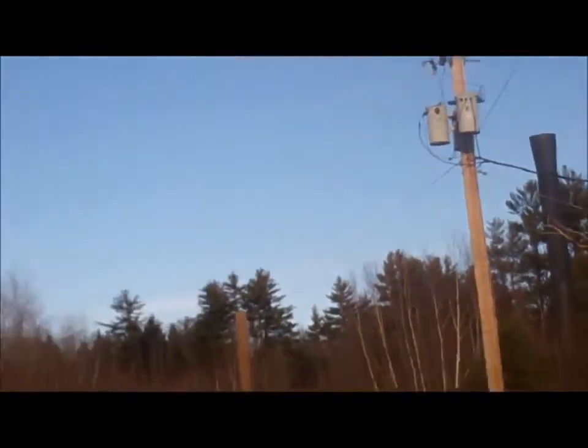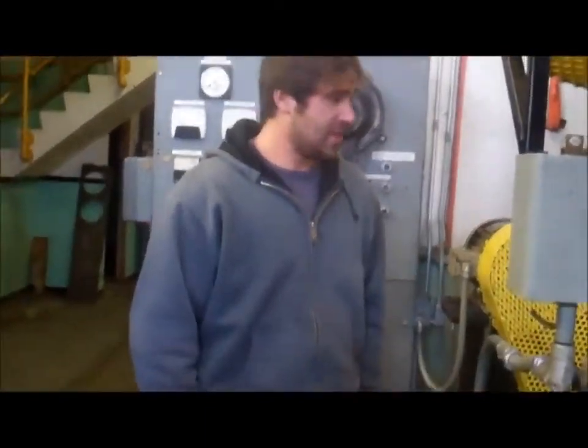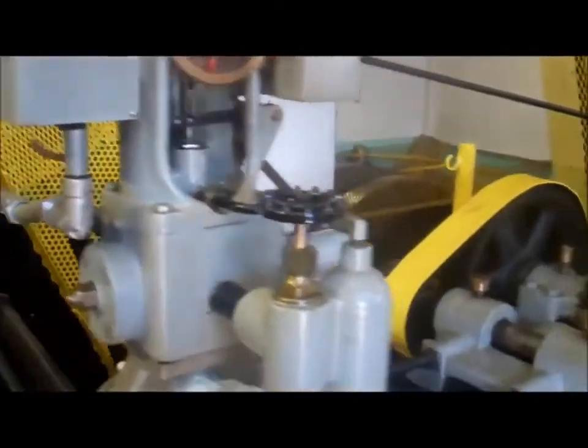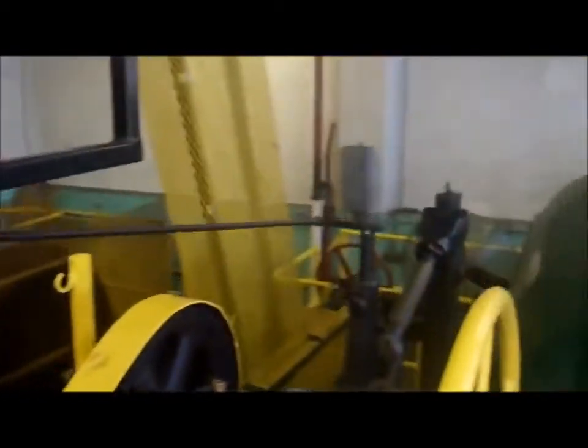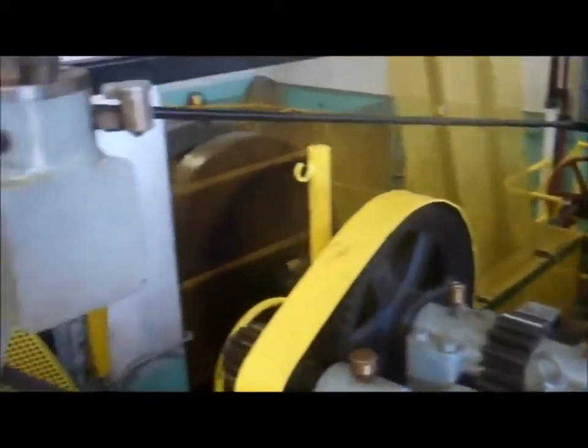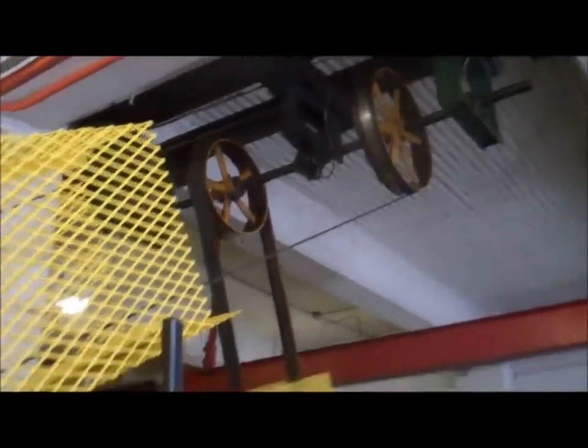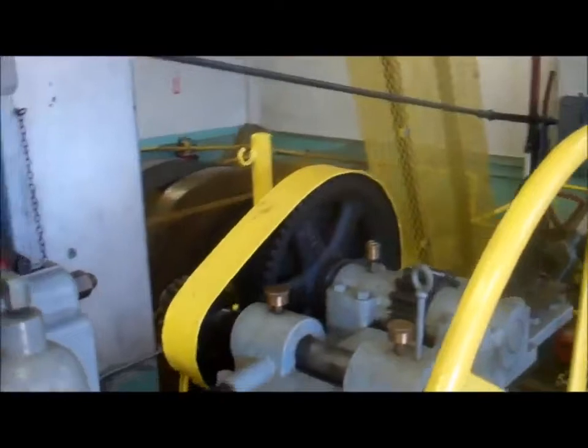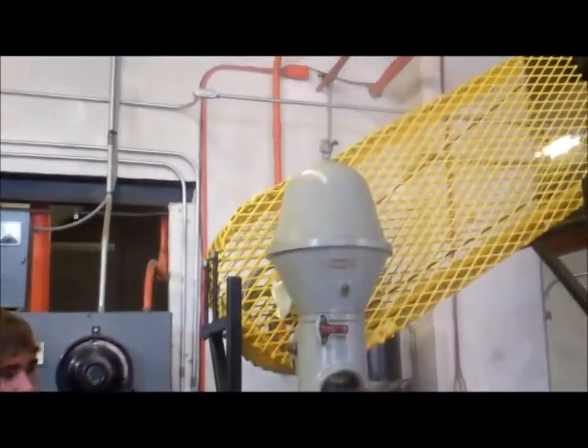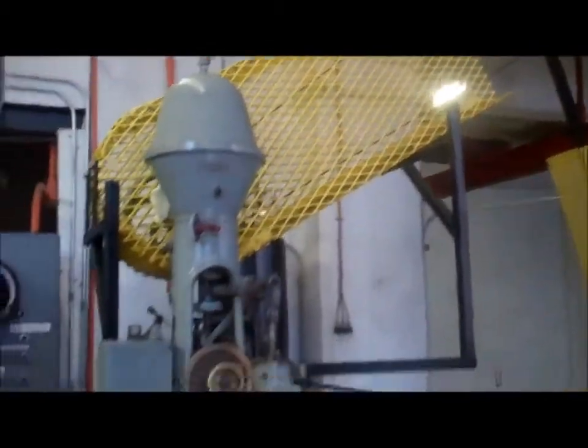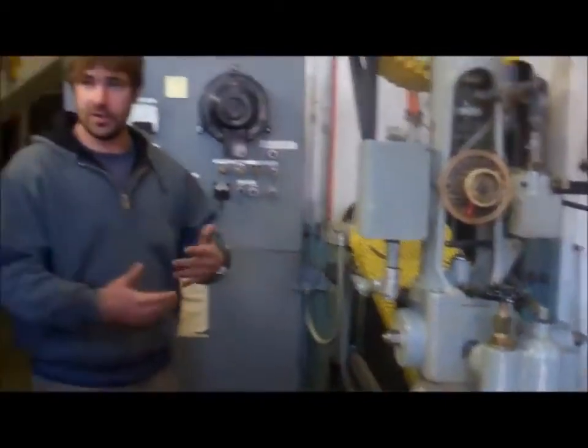I can show you guys in here. This one's shut down, so it's a little bit quiet. The water hog, this is the last one on, first one off. It's the least efficient, and this is what used to run this whole building. And this shaft used to go 600 feet the length of the building, and it was belt driven. This was a weatherboard, paper place, and all the equipment, 5 stories up, 2 stories down, was belt driven off of this machine. It's about 1,000 brake horsepower, and this is the original governor for it, because before it was used for electrical generation, they had to govern the speed for their equipment.